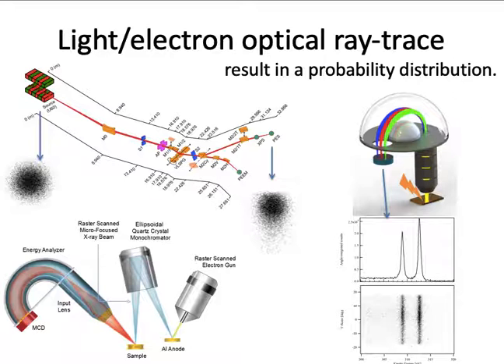When we measure the XPS spectrum, it is not as simple as carbon 1s being exactly 284 eV — the spectra show broadening. This is because the beamline, electron optics, and electron energy analyzer all have a finite broadening effect in energy and spatial resolution. This is also true for standard XPS: the X-ray source and electron energy analyzer have resolution limits, so we see the peak broaden depending on the settings of each optic.